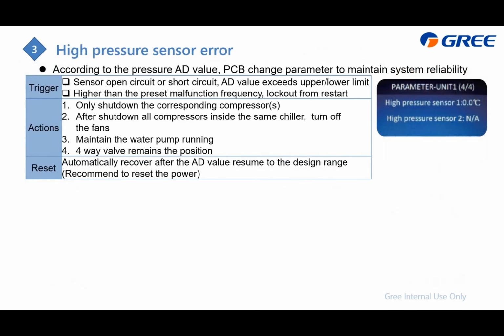And the next is the high pressure sensor error. This time it is just the sensor itself, not the system detecting it, which means according to the pressure AD value, we get it from the sensor. The PCB will always change the parameters, like the compressor RPM or the fan RPM and even the ESV opening, to maintain the system reliability. And maybe this pressure sensor is open circuit or short circuit, which leads to the AD value exceeding the limit.